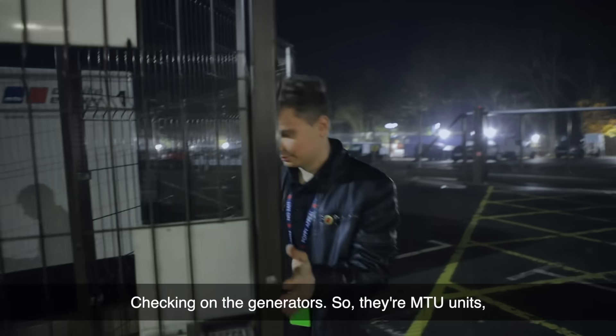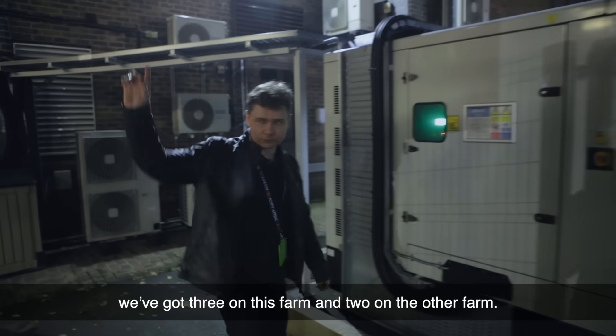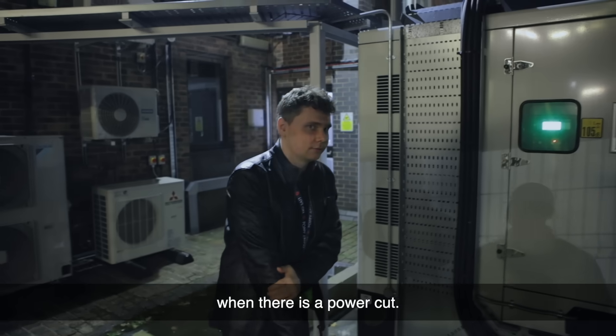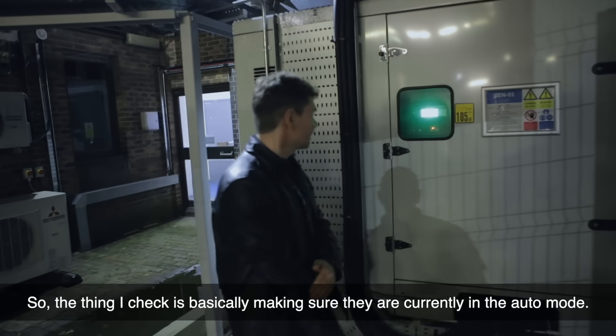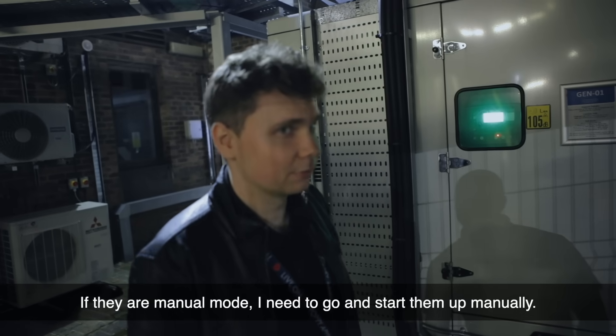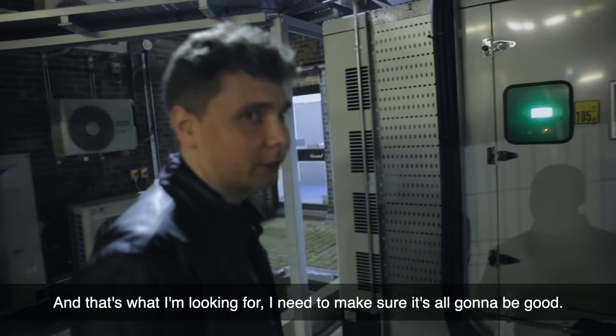Checking on the generators. So, they're MTU units, we've got three on this generator farm and two on the other farm. All of them together are capable of running the entire data center if there's a power cut. The thing I'm checking for is making sure they are correctly in auto mode. If they're in manual mode I need to go and start them manually. Obviously in auto mode they detect the problem themselves and start running.